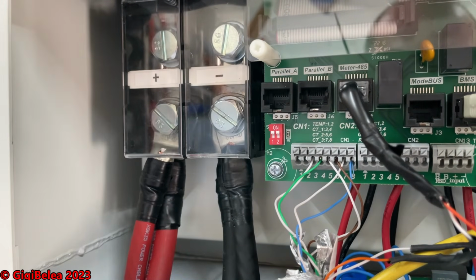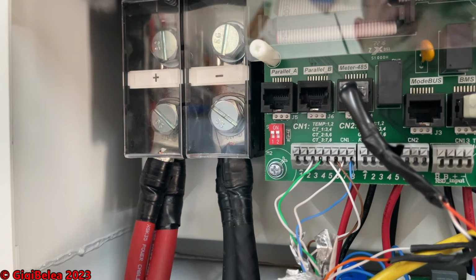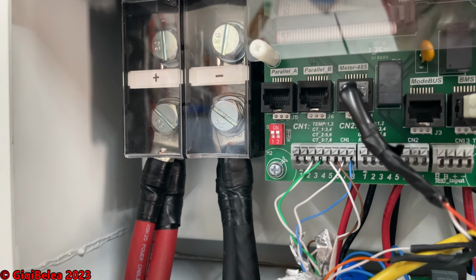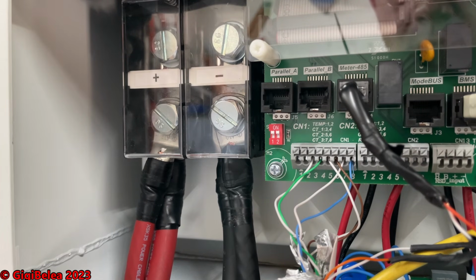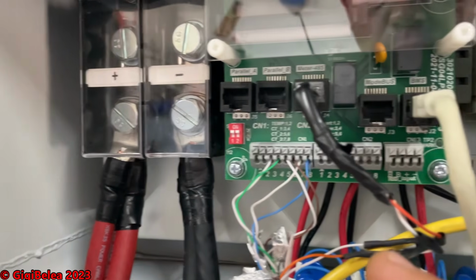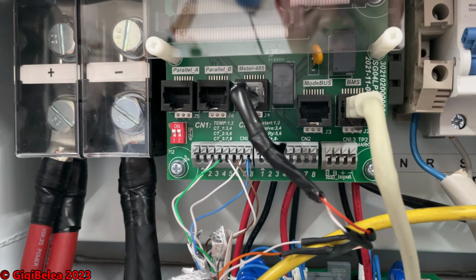Then down here I have the CT coils, so this inverter can work both with CT coils and the smart meter. I have both connected. Why? Because in case of failure of the CT coils or the smart meter - actually the primary is the smart meter - so if the smart meter fails, the CT coils will take over. I had some issues with the smart meter connection, that's why the cables here are messy, I was fiddling with them. With the newest firmware this problem seems to be gone, so I can actually pack up and make some nice connections here.